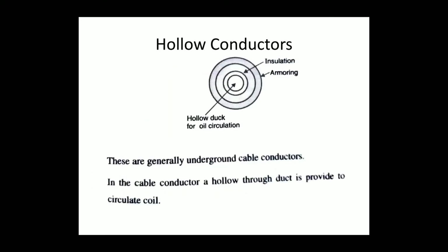The next is the hollow conductor. These are generally underground cable conductors. In the cable conductors, a hollow through duct is provided to circulate oil. This part is a duct, this one is the hollow part, and because of this hollow part we reduce the skin effect, which was already discussed in topic number 2.